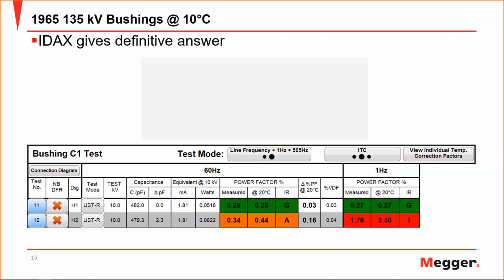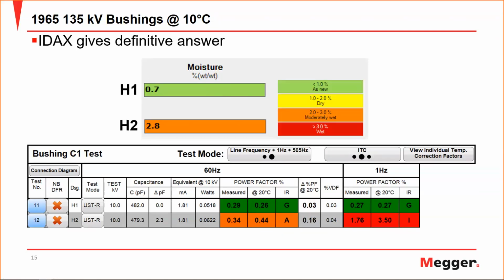And for this particular customer, when they brought out the IDAX, when they tested the H1 bushing, they saw that the moisture was low and was within a good range. But that H2 was showing service aged, moderately wet, and almost approaching very wet. So again, the 1 Hertz will not tell you what is wrong or where the problem lies within your particular asset, but it can direct you where to focus your additional maintenance and test efforts, which is really what we're all trying to do in the world today.